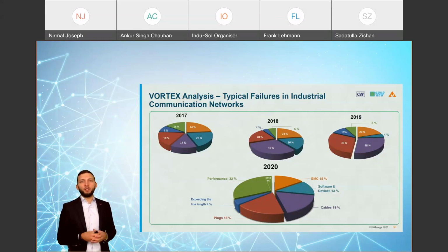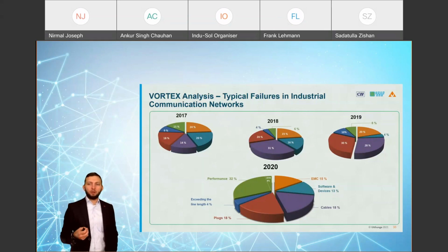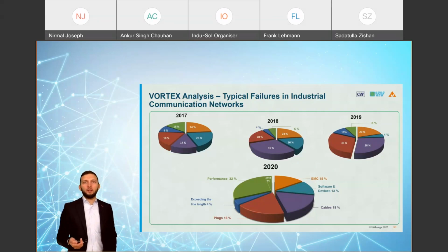Or maybe I have to monitor the performance, so that I can find some indicators telling me I have to change something. And the third biggest part is the EMC topic. Maybe I have some frequency converter inside my network or installation, and through this motor cabling I have an impact on my data lines. This impact is a high current on my shield, for example. Through this current, maybe I destroy some devices, or I destroy the communication in my line. So these are three big topics in our daily service work.